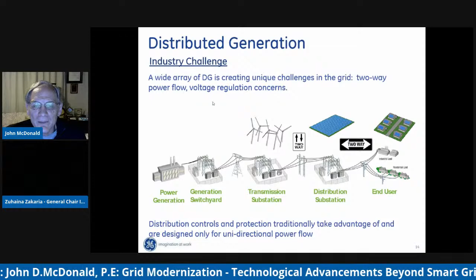So some of the industry challenges: we have open circuit overvoltage due to unintentional islanding, and we have protection ratings that may not match our fault currents. Why is that? Well, when we did our short circuit studies to determine our protection settings, we typically modeled the grid and really considered the source side contribution to the fault only.